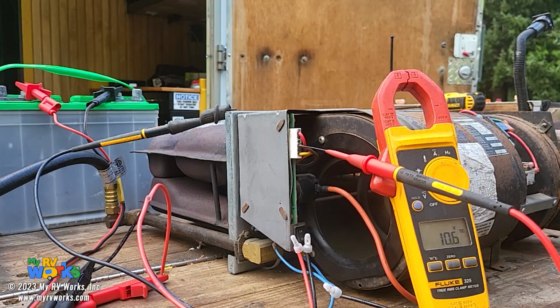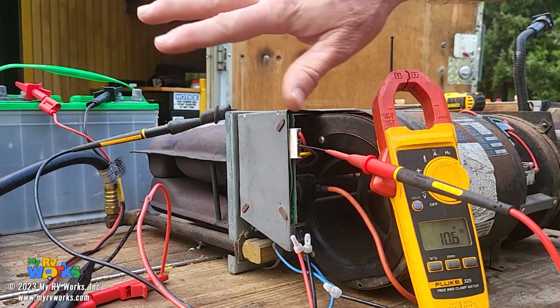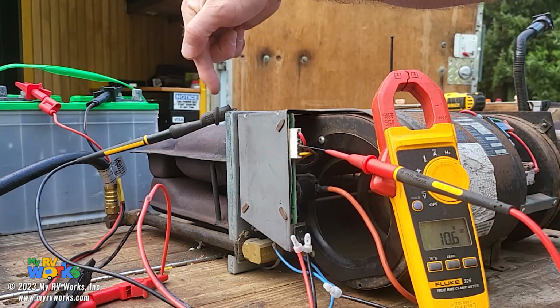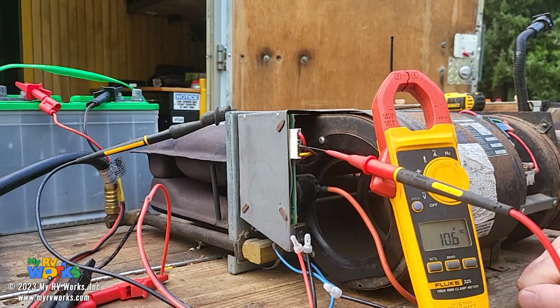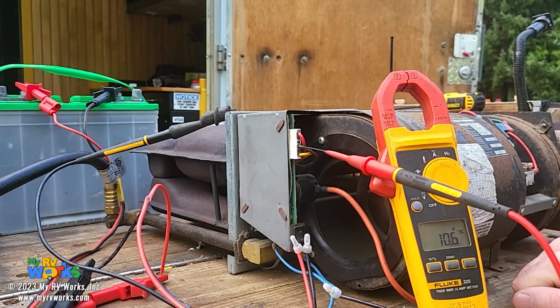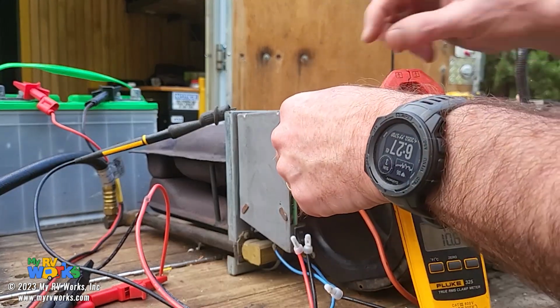Okay, so all this is to say, now the yellow wire is ground, so we could reference ground, but you see I've got it right here grabbing the frame. Now that I've gone through all that, let's benefit from this furnace having an intermittent issue. If I want to eliminate the sail switch and the high temperature switch as the problem, then I can reference this red wire up on top.